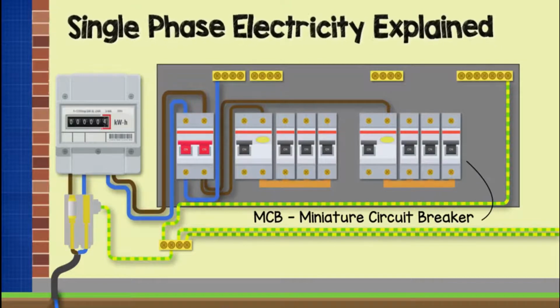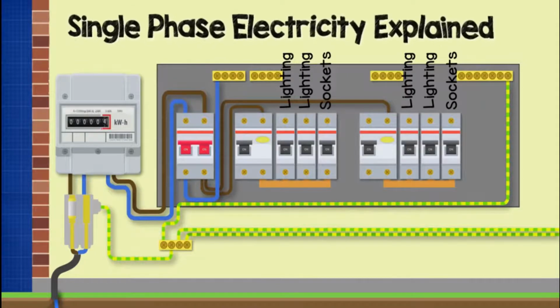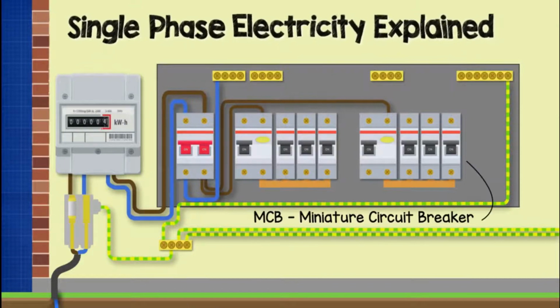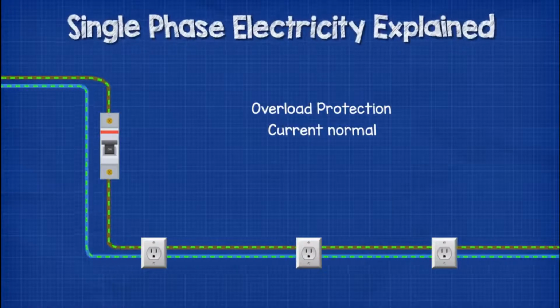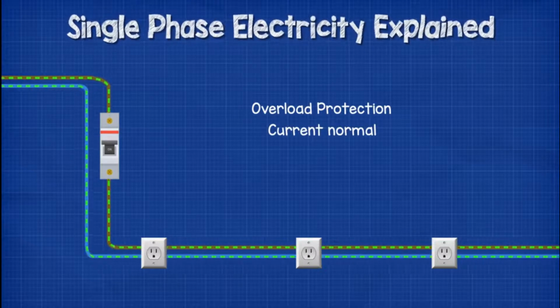The MCB or miniature circuit breaker controls individual smaller circuits. For example, connected to one RCD, maybe we'll have one MCB for the downstairs lighting, one for the upstairs lighting, and one for the kitchen plug sockets. On the other RCD, maybe we have one for the stairwell lighting, one for the upstairs lighting, and one for the downstairs plug sockets. The MCB is rated to handle a certain amount of current passing through it, for example 32 amps for the plug sockets.